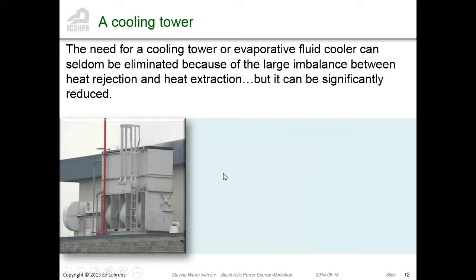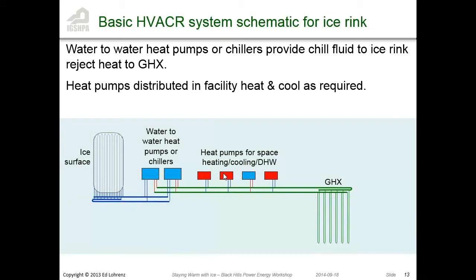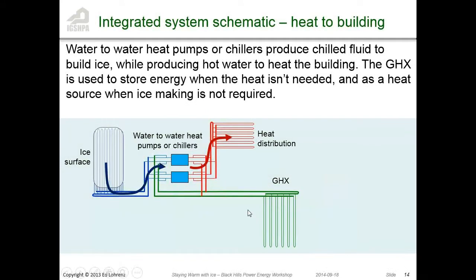And a real simple way of doing this on a number of smaller rinks, the simplest way, is connecting the chillers, running the condenser to a ground loop, and then using heat pumps within the building or in other buildings nearby to extract heat from the ground loop. They're going to run very, very efficiently. You've got a 60 or 70 or 80 degree ground loop in the middle of winter. Another way is to use the same heat pumps. You can just direct the flow of hot water either to the building or to the ground loop.